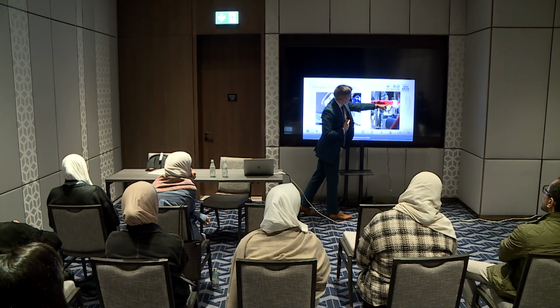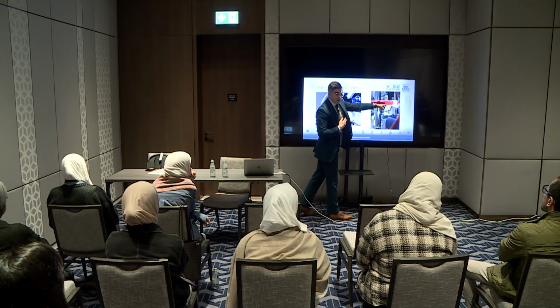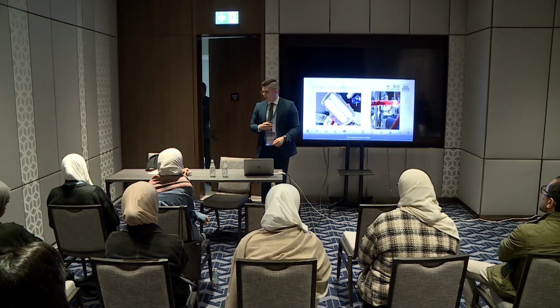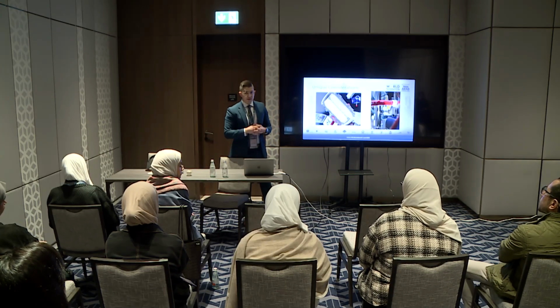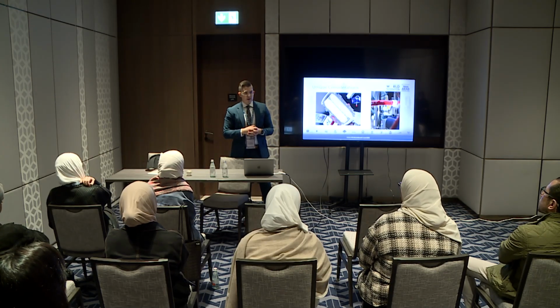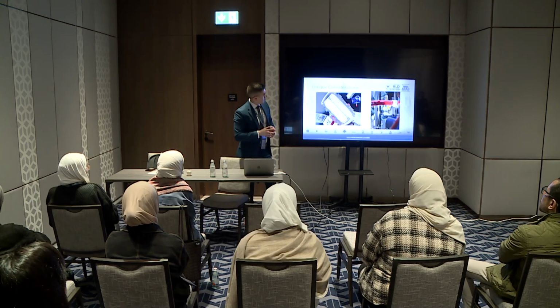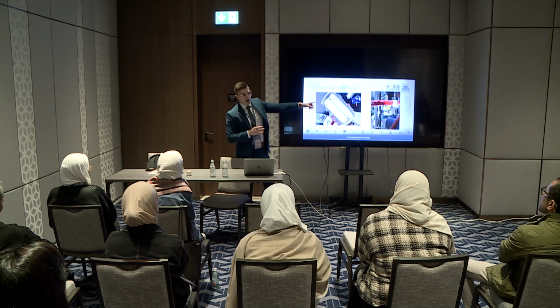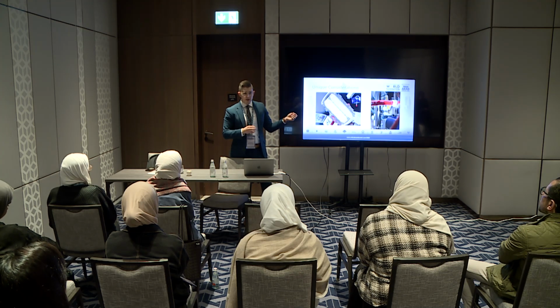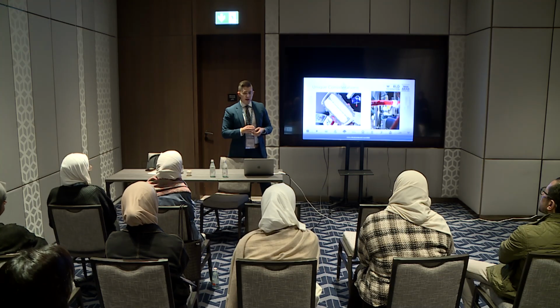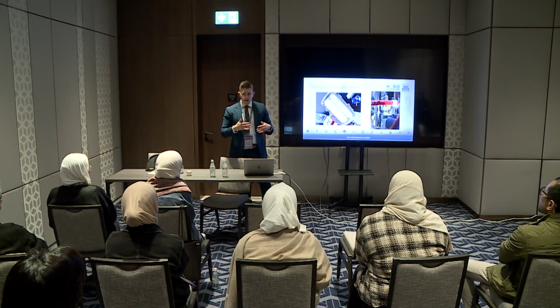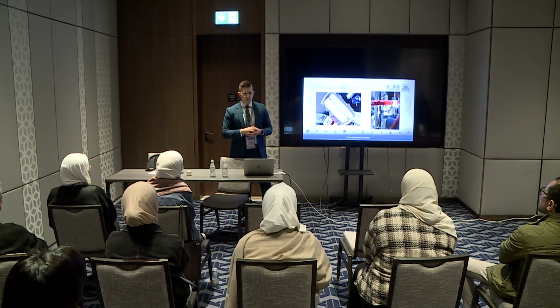And what I've highlighted here, hopefully you can see it, this is some fibrin. So fibrin that started to grow off of this connector. And this can be very problematic for specific types of ECMO support where it can be very risky. So this picture I took on the right-hand side, a patient on VA ECMO, cardiac ECMO. And so this line that is returning oxygenated blood to the patient is directly into an artery. And so if that fibrin embolizes off, it goes straight to the brain, spleen, kidneys, and has a very big consequence.